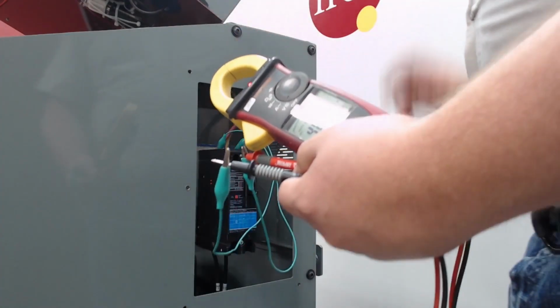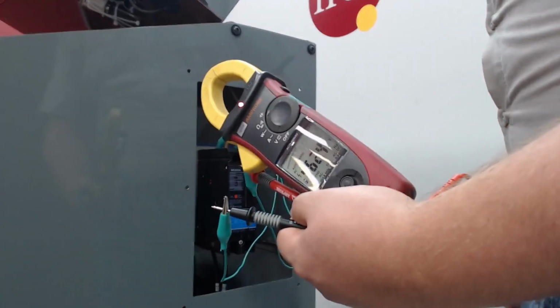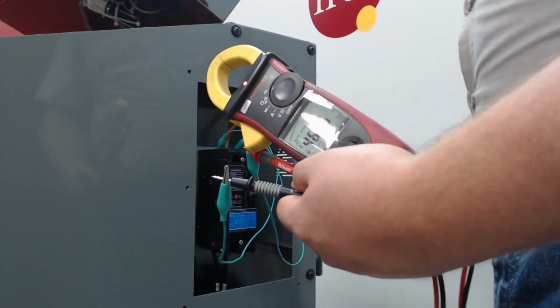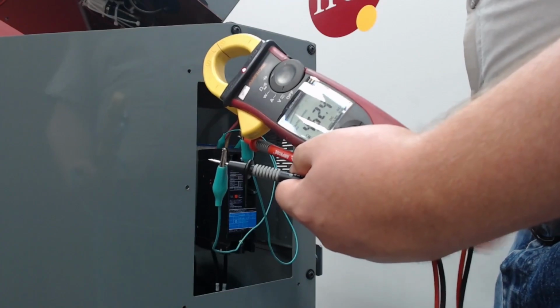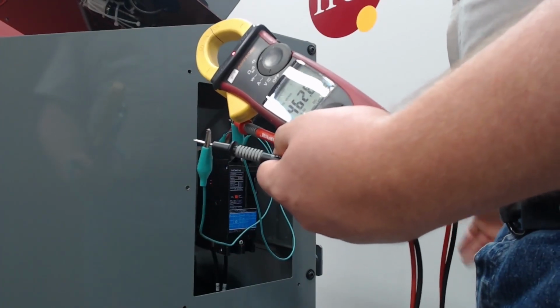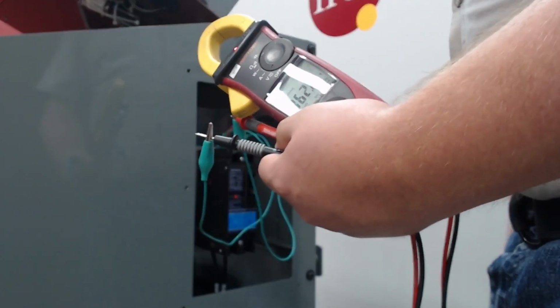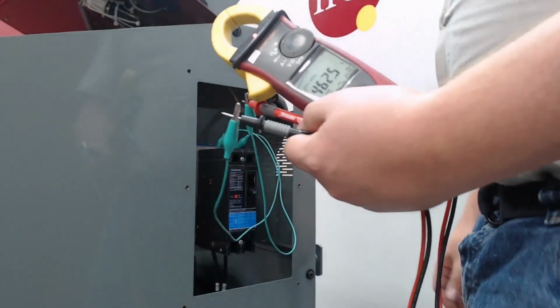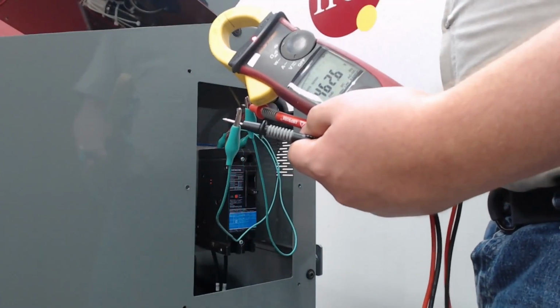So this unit here is a 460 volt. We're at 462. We're right at that nominal voltage. Maybe you'd be running 440, maybe you're running 480. Just depends. There are some settings you can change to adjust that, to accommodate it, but we are nominal, so we are good. I'm going to go ahead and turn it on.